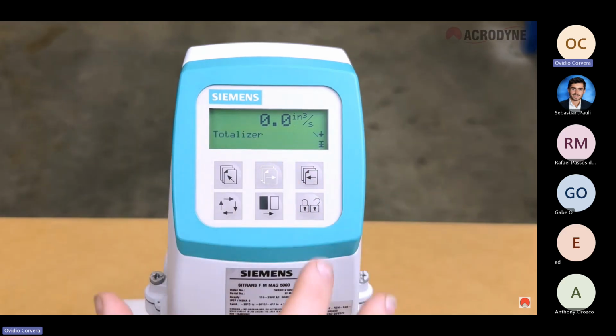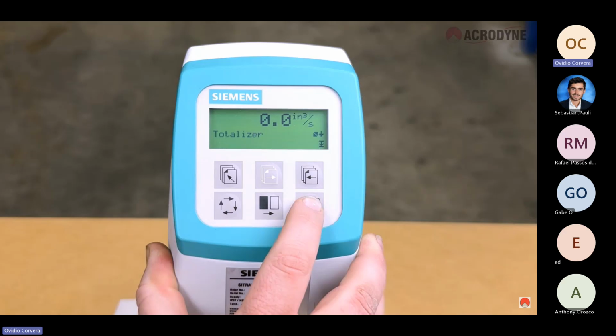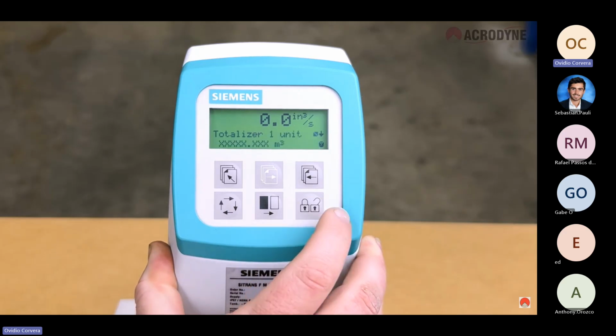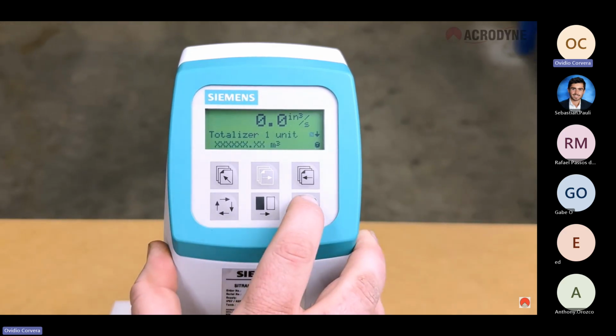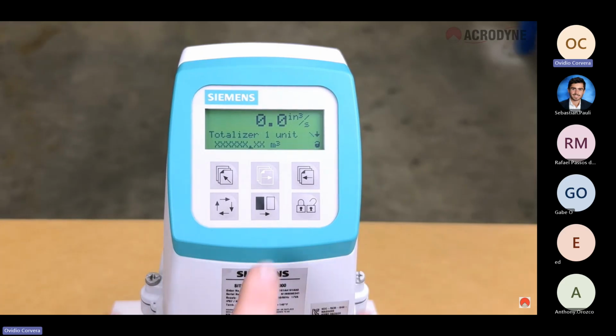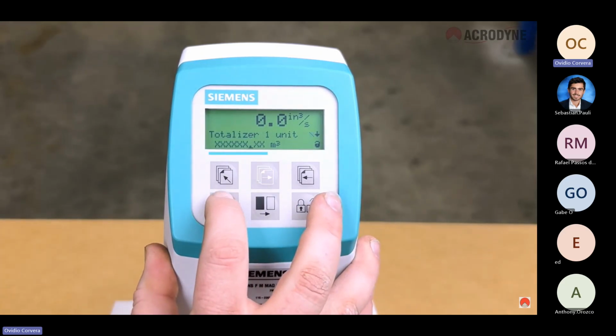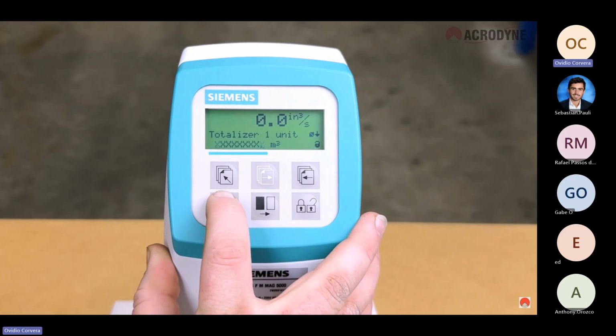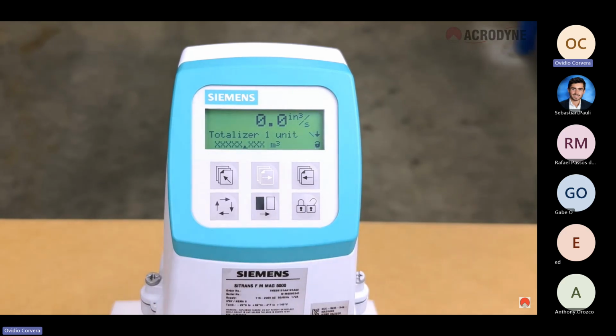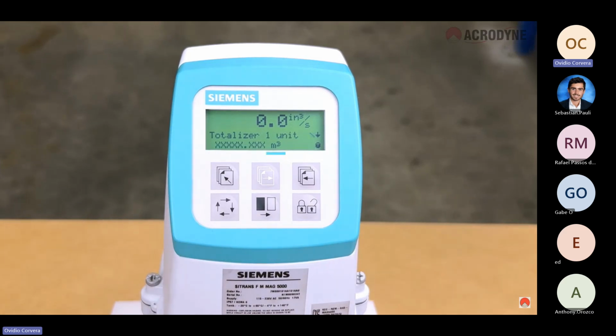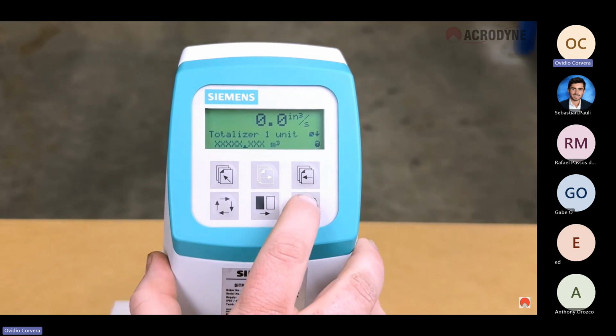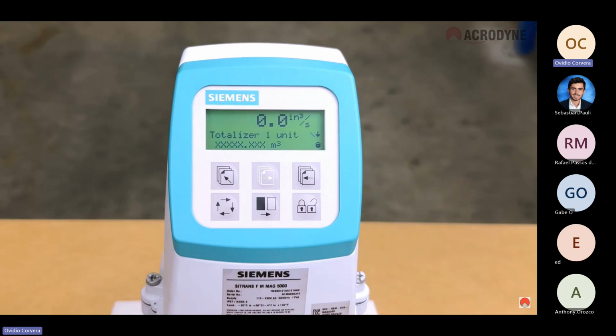Totalizer. Press the lock or unlock key to access the Totalizer 1 screen. And then press the lock or unlock key a second time to edit the settings. Now press the change key to move the decimal place to the desired location. This is how it will be shown on the main display when in use. Once the decimal place is set, press the select key to access the units option. And if required, press the change key to alter the settings to the desired units of measurement used in your environment. Finally, press the lock or unlock key to save these settings.